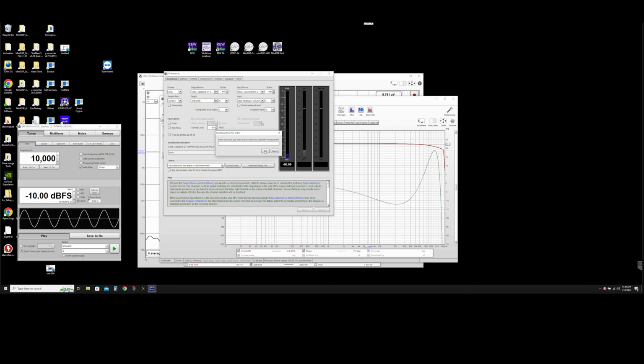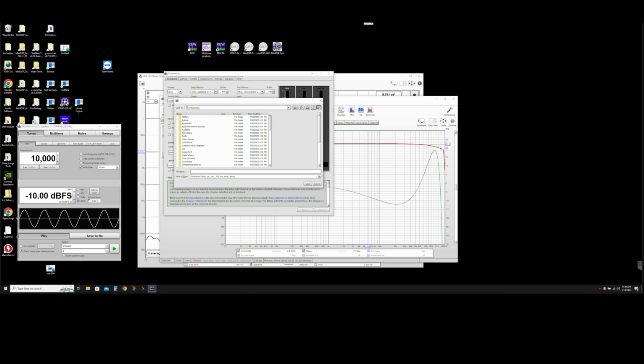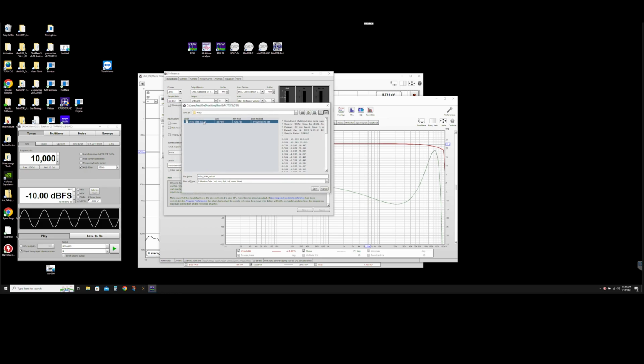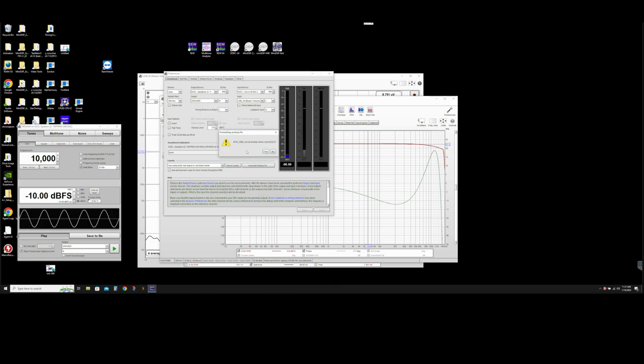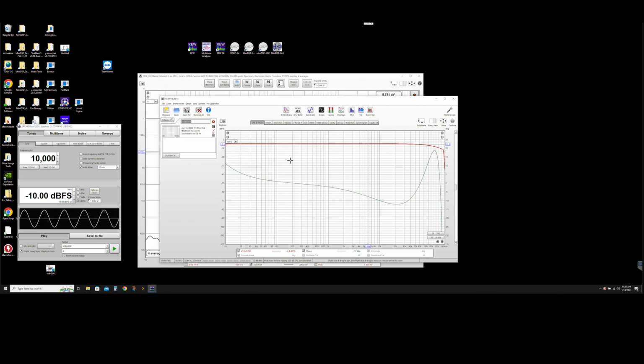We can add notes if we want. Save it off somewhere. I'll save it as this because I took it at 384. If you use a different sampling rate, you should create cal files for each sampling rate. So we'll save that. Now I don't like to apply the calibration file to all my measurements. I only like to apply it to frequency response.